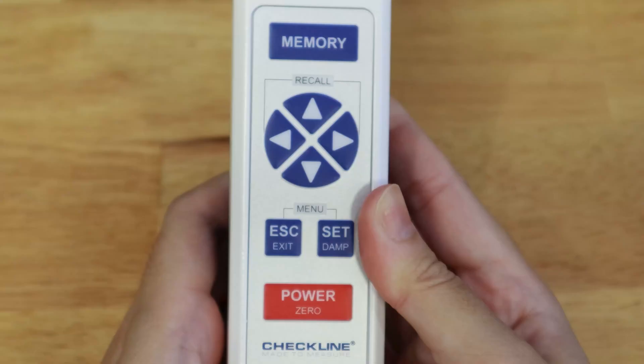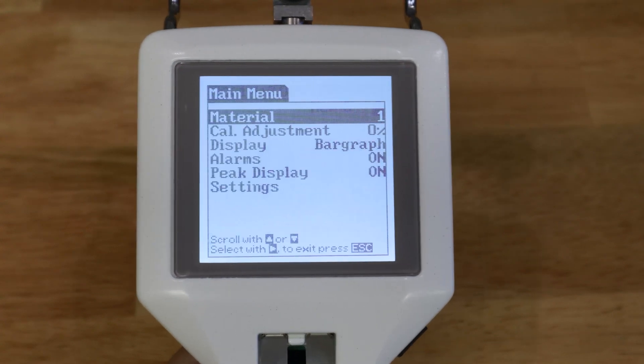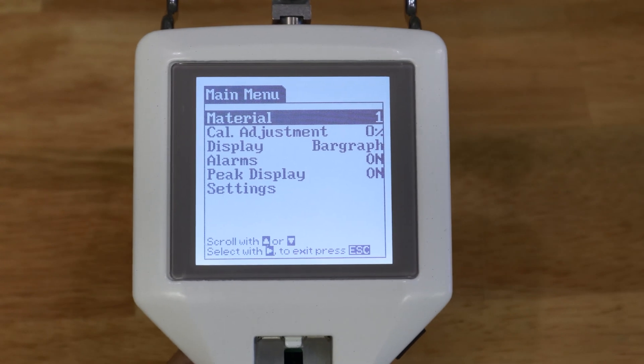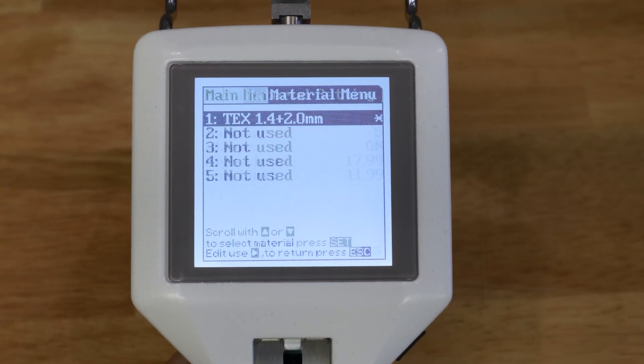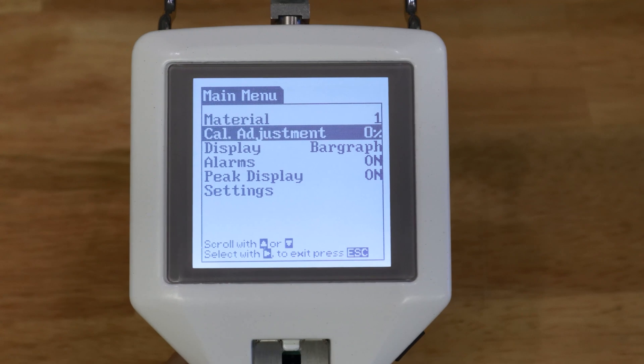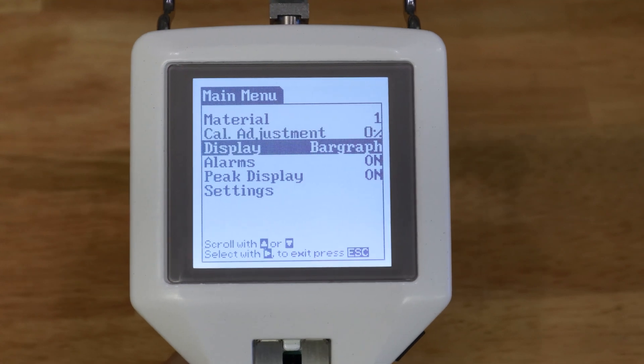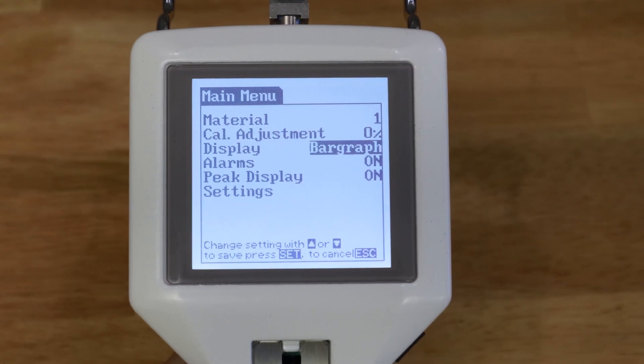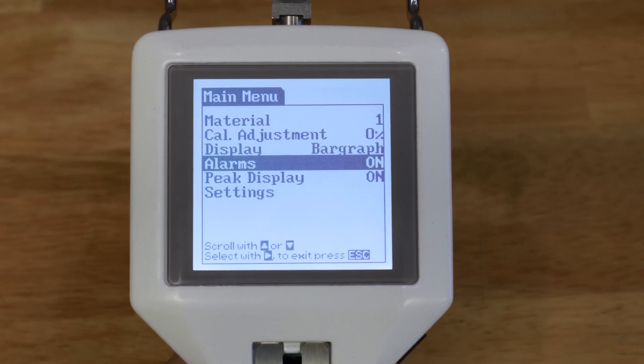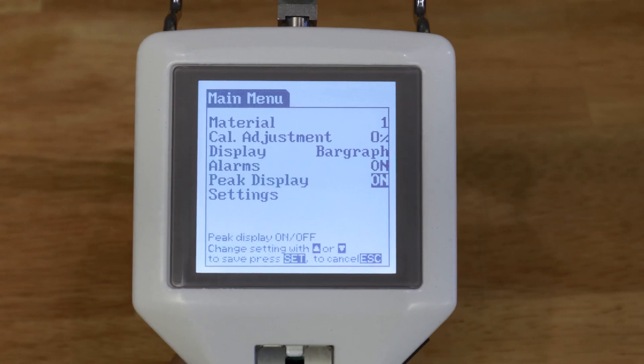For the features inside the device, we will start with the menu by pressing the Escape and Set buttons simultaneously once. The screen will change to the settings menu. In the Material menu, you can set up to 5 material detail slots and recall them for future use. The Cal. Adjustment menu allows calibration. The Display can be set in 3 modes: Bar Graph, Graphic, and Numeric. You can also enable or disable the alarm sound in the Alarms menu, and display Peak values on screen in the Peak Display menu.